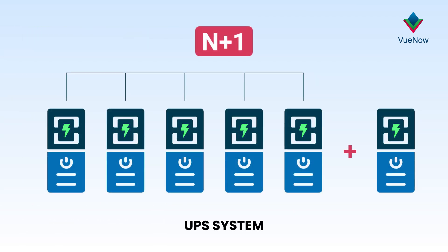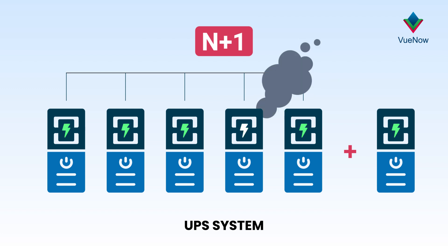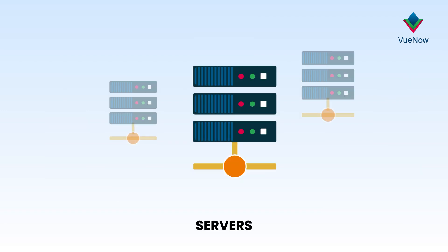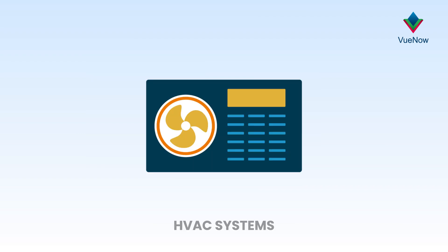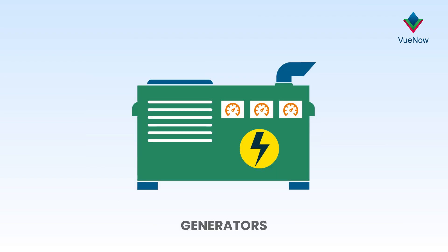N plus 1: similarly, if a datacenter needs 5 UPS units to operate, an N+1 plan means 5 plus 1. That way, if one UPS unit fails, there is an extra UPS that can kick in to pick up the slack. This applies to all types of components — servers, storage hardware, HVAC systems, and generators.